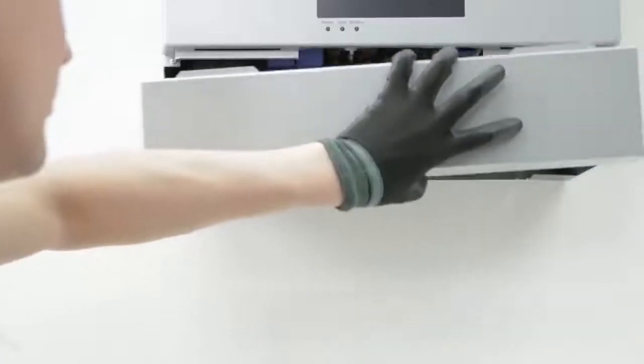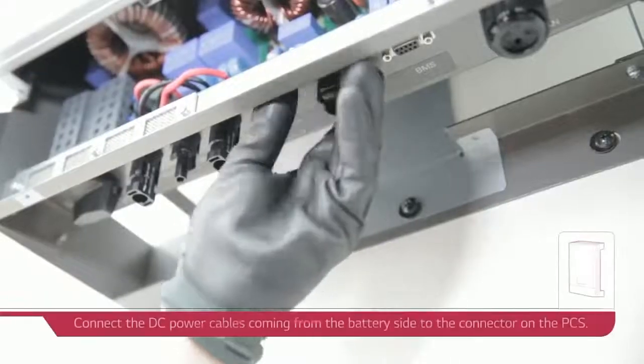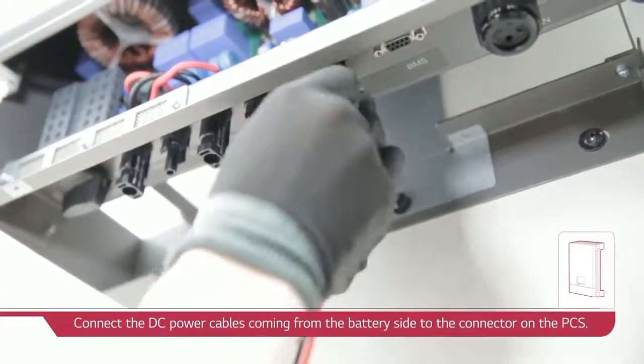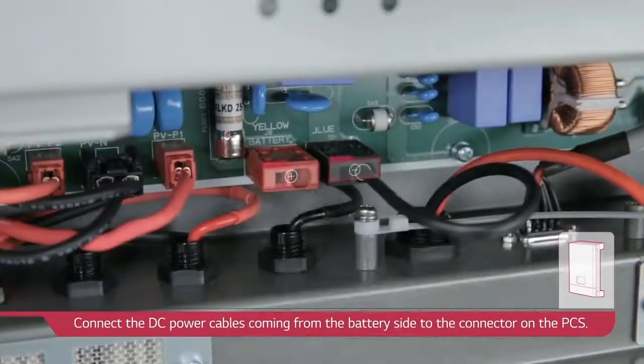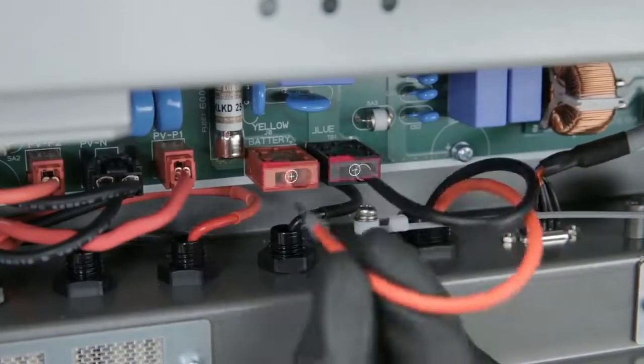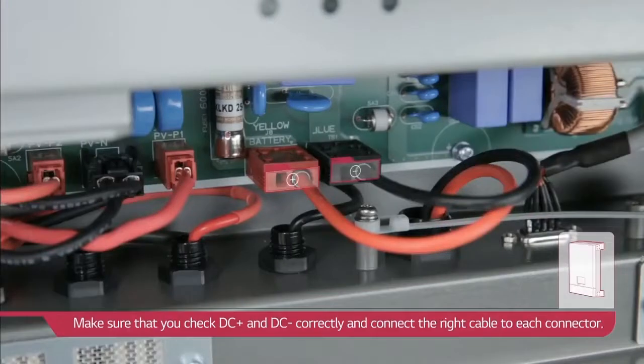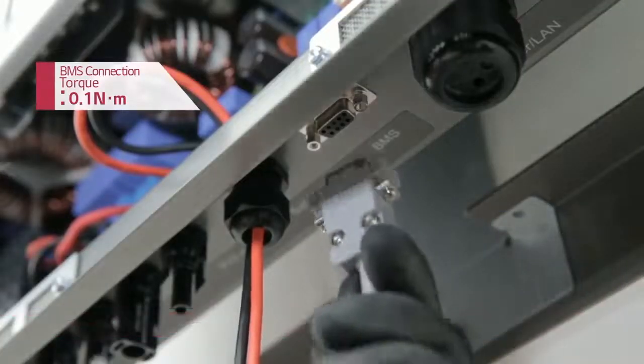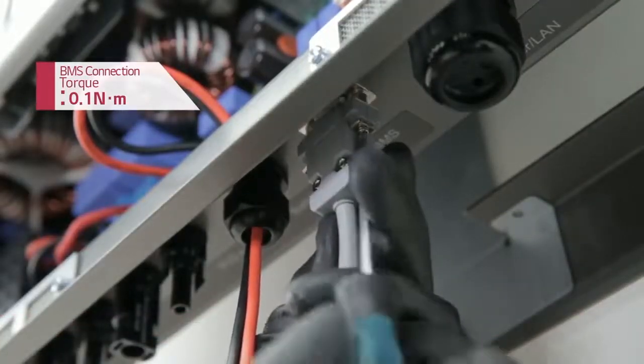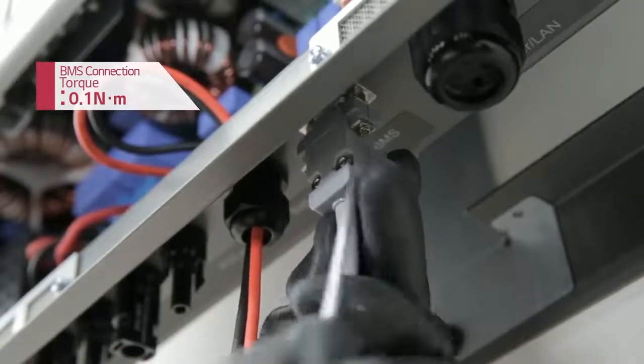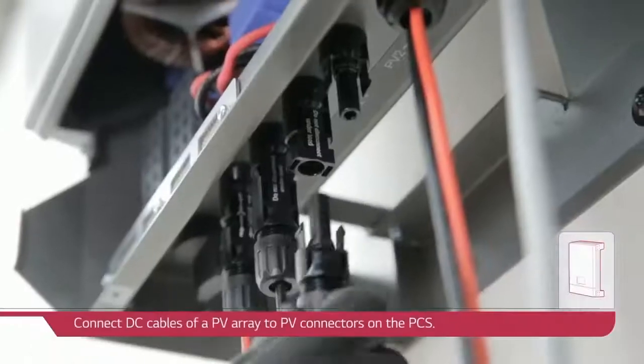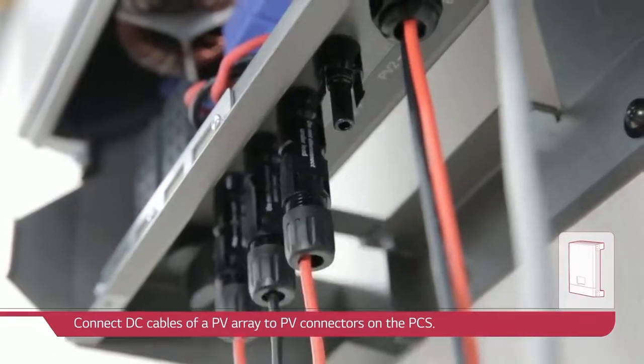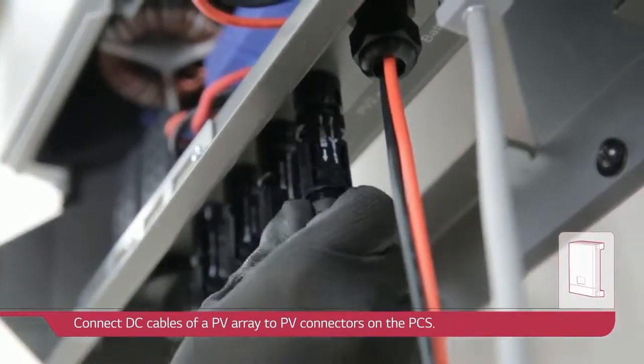Disassemble the lower cover from the PCS. Connect the DC power cables coming from the battery side to the connector on the PCS. Please beware not to be confused with the polarity when connecting the cables to the connector. Make sure that you check DC plus and DC minus correctly and connect the right cable to each connector. Connect the battery management system cable coming from the battery side to the BMS connector on the PCS. Connect the DC cables of the PV array to the PV connectors on the PCS.